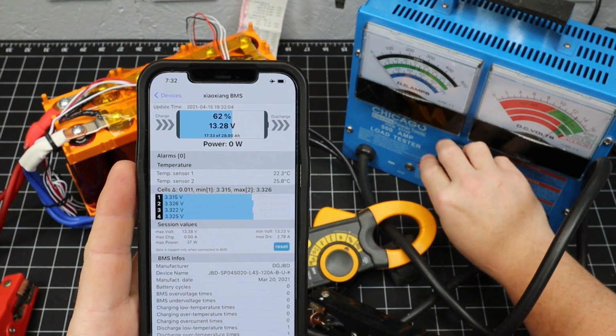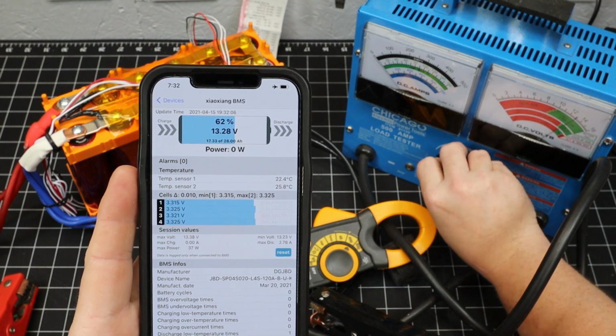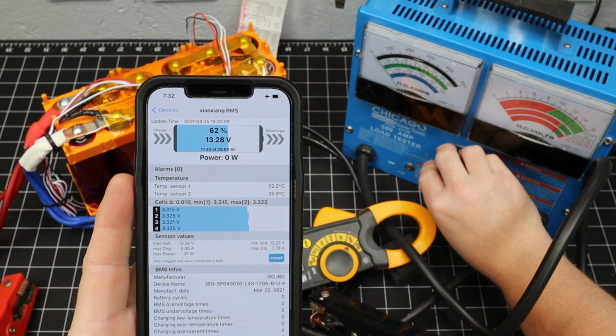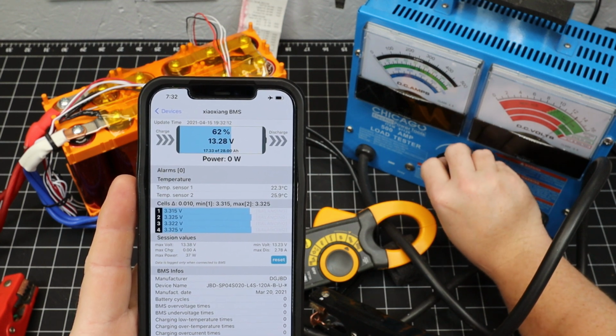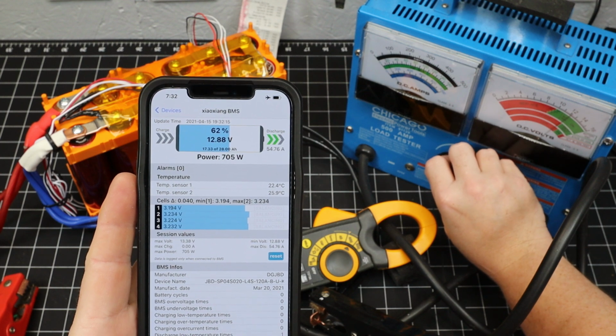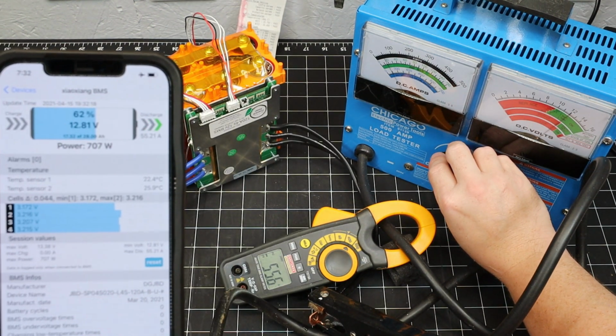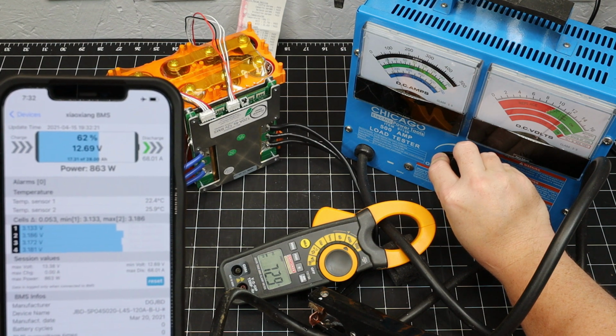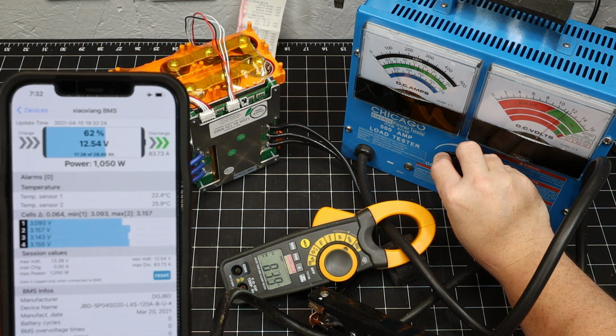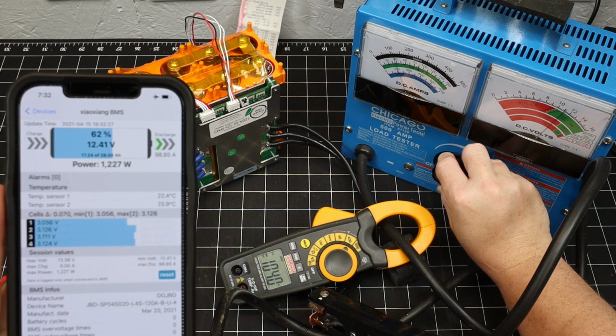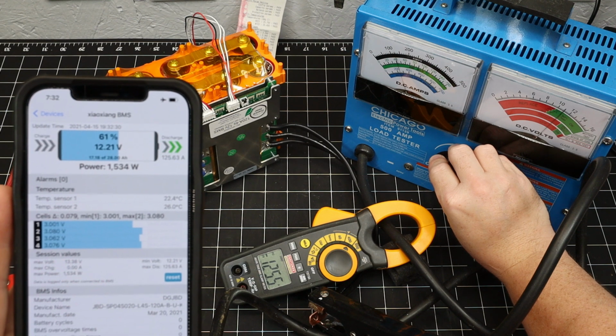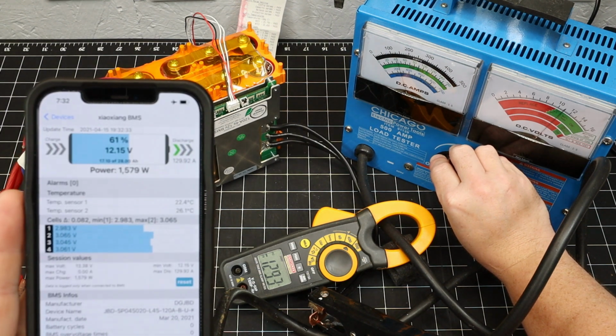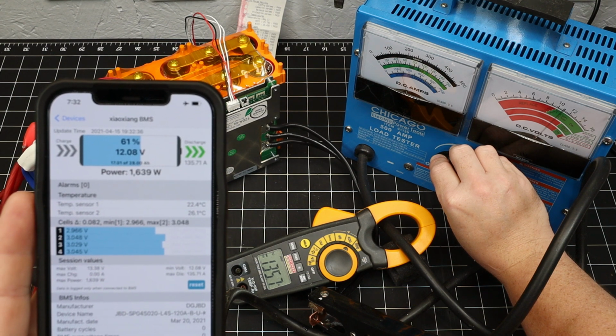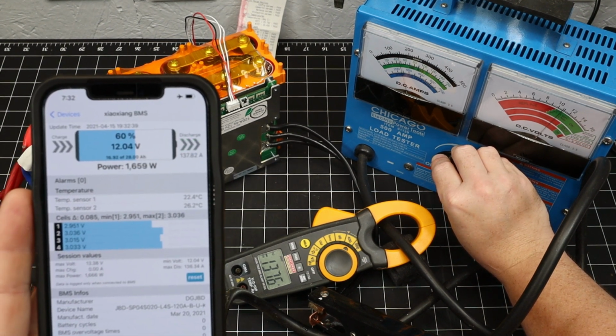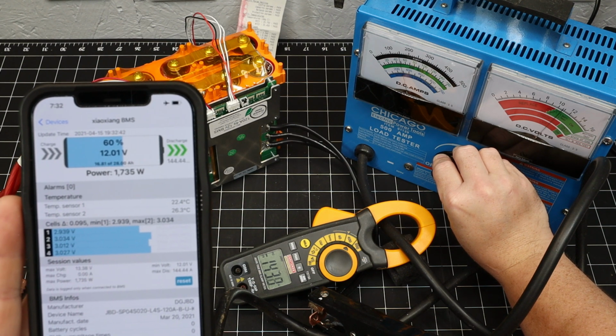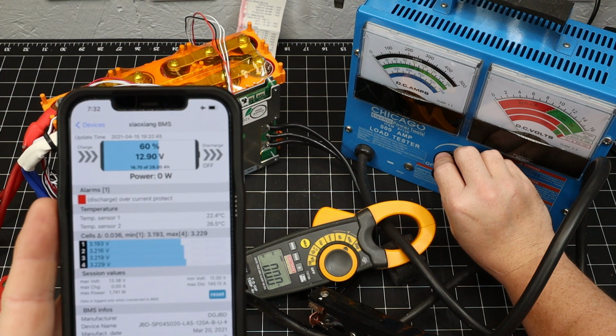Now don't be surprised if this thing starts smoking. I've pulled many 500 amps with this one. Alright, there's close to 52 amps. 72, 83, and it's starting to smoke already. So let's go ahead, there's 121, 127, 130, and the BMS has not cut off yet. We're at 142, 147 -- oh, it cut off.